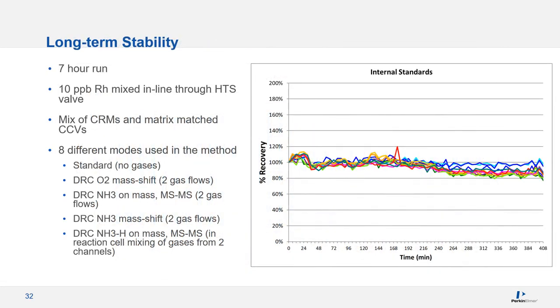Long term stability was verified during a seven hour analysis of the lithium borate fused samples. The analytical run consisted of multiple fusions of each CRM, matrix blanks, and simulated samples in the same fusion matrix, all to demonstrate the effect of analyzing samples with high total dissolved solids on the sample introduction and internal components of the Nexion 5000 ICP-MS. Eight different modes were used in the method, switching between multiple gases. All internal standards recovered within 20% of their values to the calibration blank initially recorded, further validating the robustness of this method and analytical instrument.